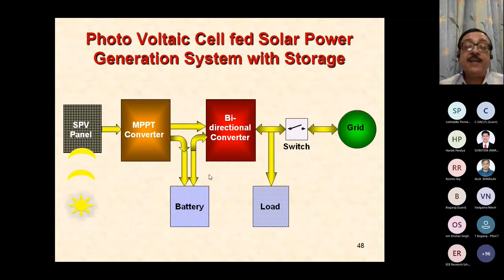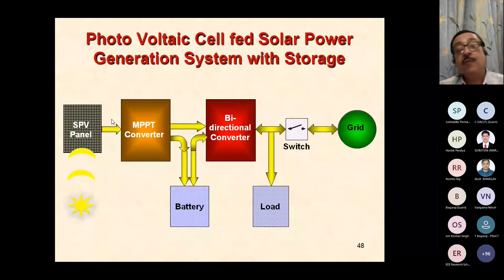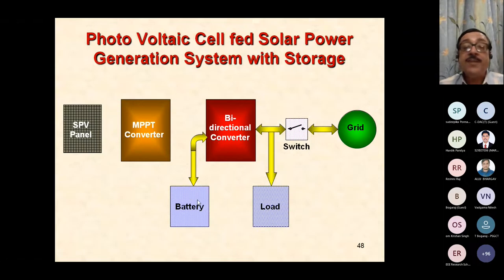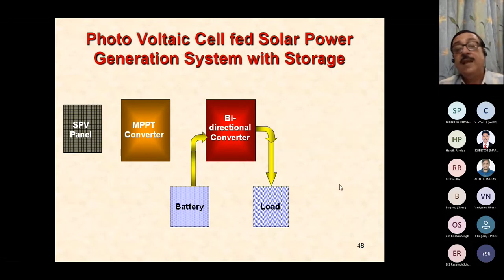It keeps operating on its own, and the MPPT keeps tracking the sunlight and the panel output power. In case there is no sunlight available, then the battery keeps supplying power, or it can be charged from the grid and keep supplying the local load, as I said. And if the grid fails, you can still maintain supply on the local load.